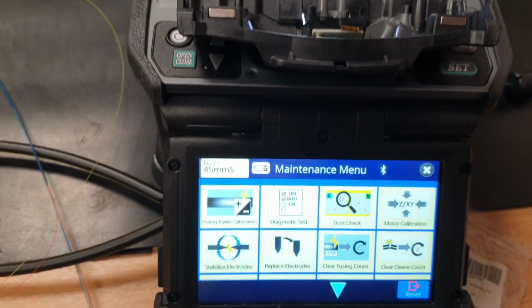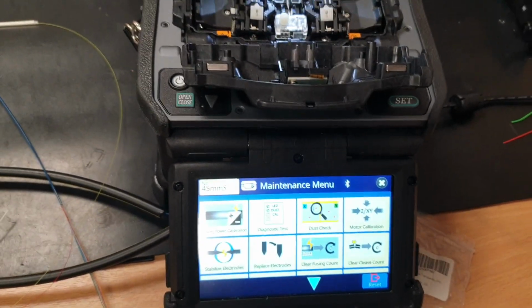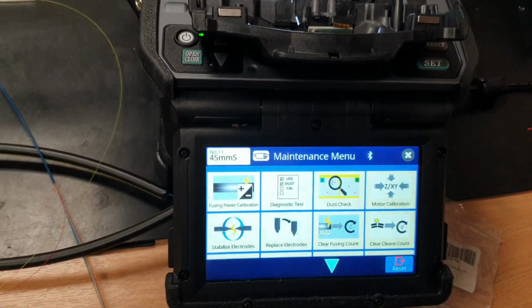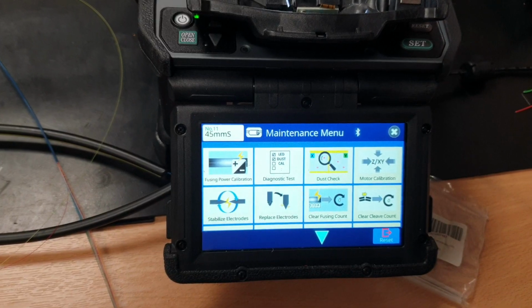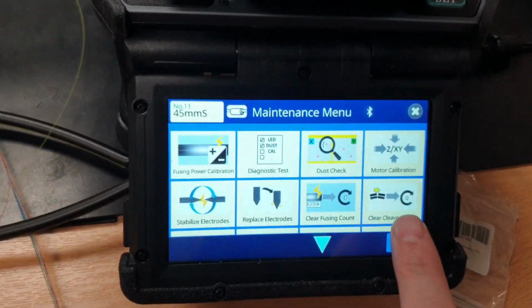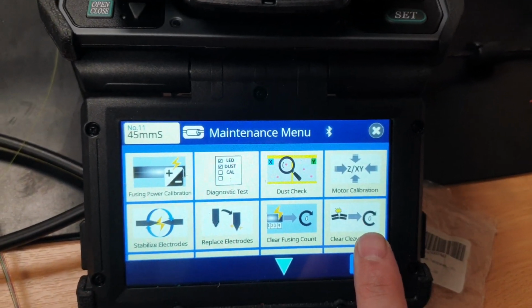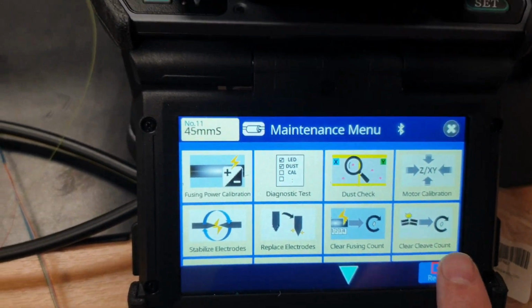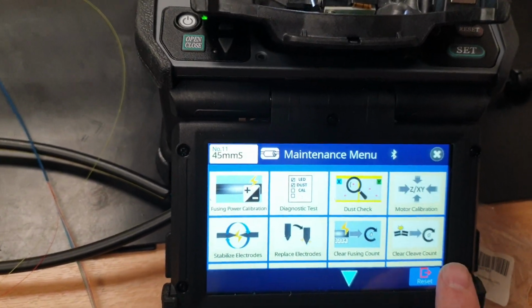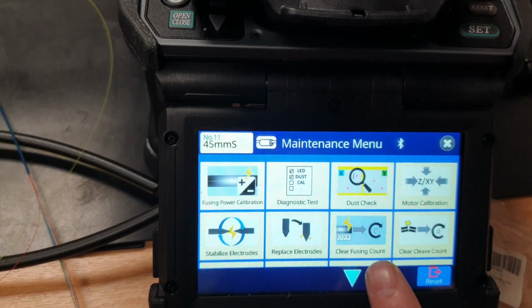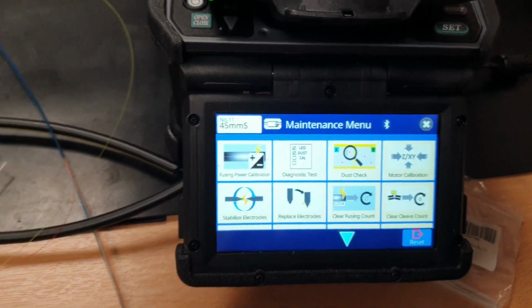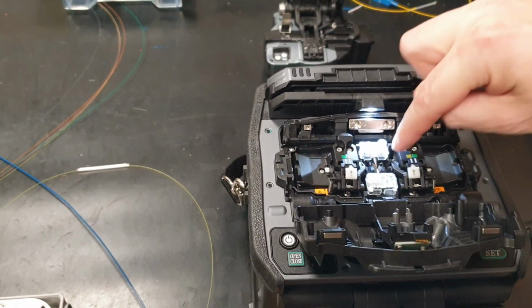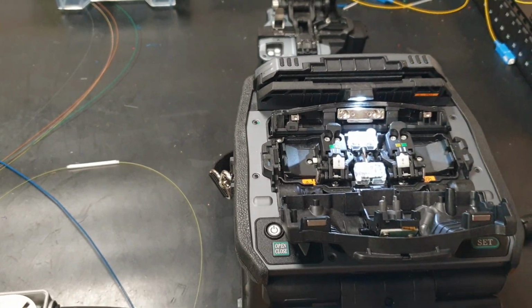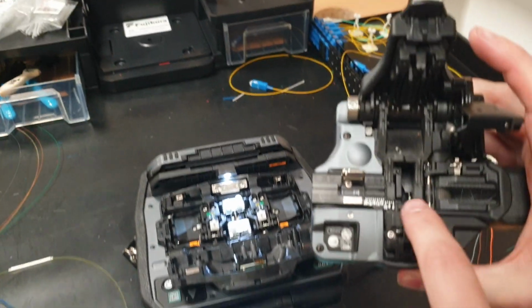Does that make sense? You actually have to check it. The machine won't give you a warning to say that you've reached that limit. No, you'd have to check yourself. If you have just changed the electrodes, yeah, you can clear the cleave count. Now cleave count is different to fusing count. Fusing count is how many times you've fused the fibres. Cleave is how many times you've cleaved the unit.